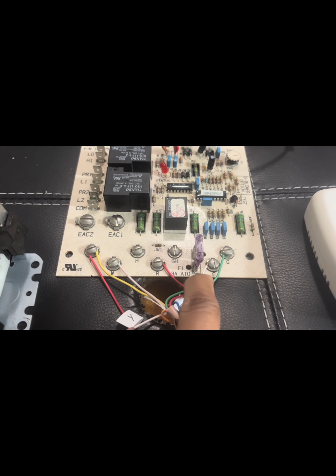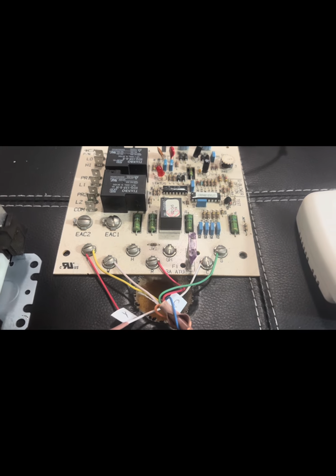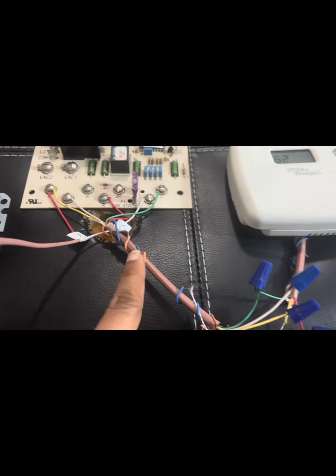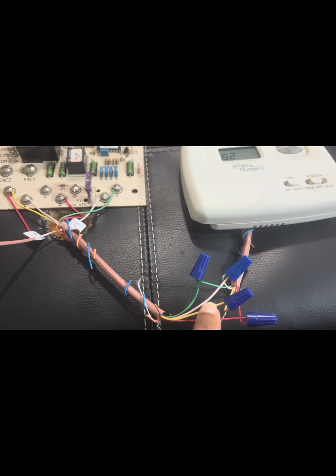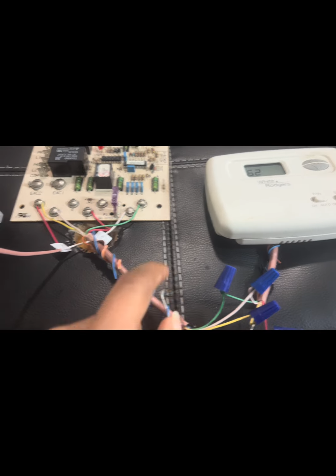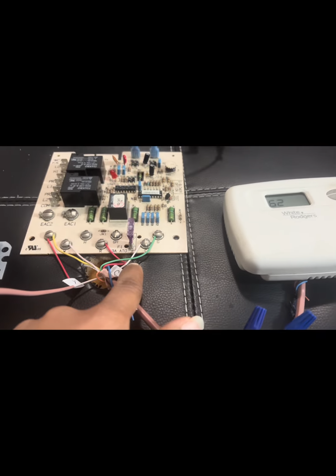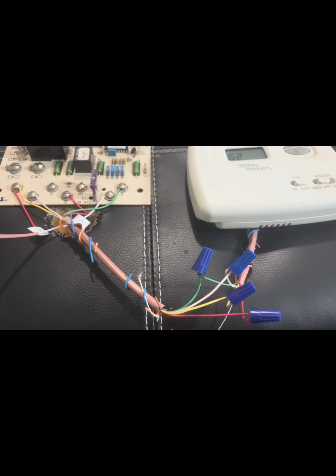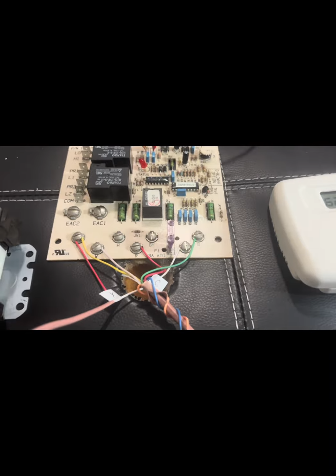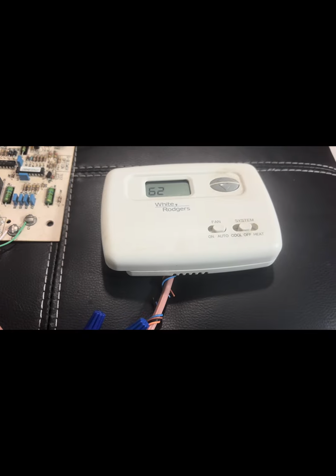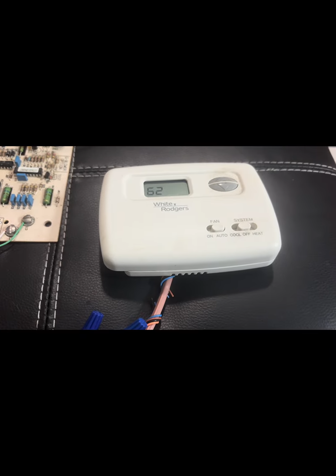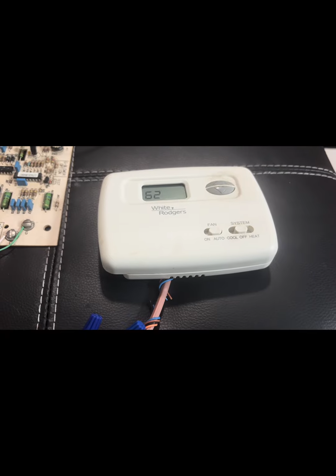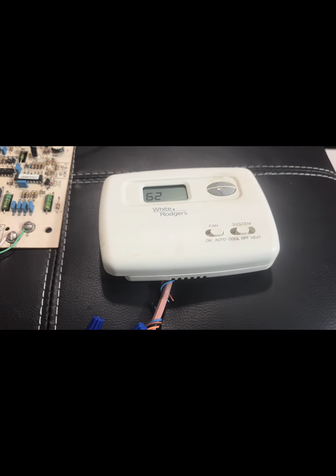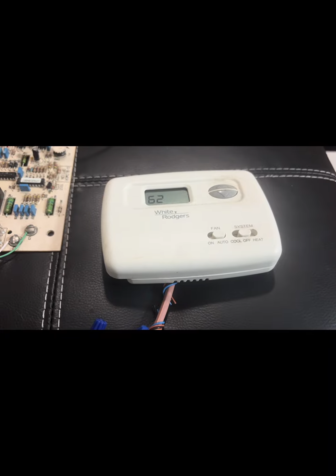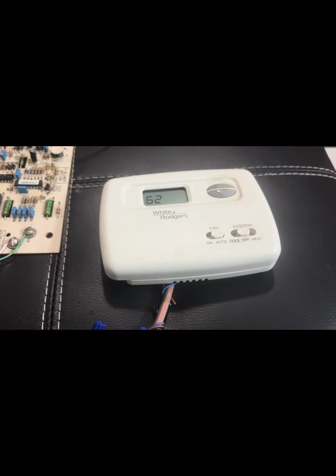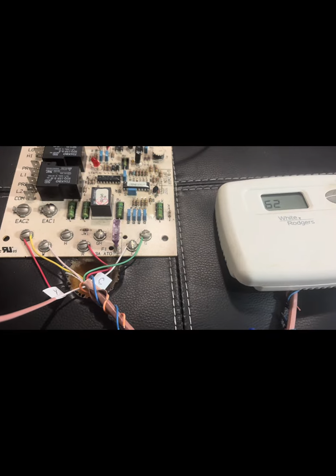Then you connect the matching wires to your thermostat. So we have that going back to your thermostat. And if we had a common one for this thermostat, we will also do the same thing. But this one doesn't have the C terminal. This way, when the thermostat sends R to Y, power flows, the furnace relays that Y signal to the outdoor unit, and the C wire completes that 24 volt circuit. The condenser contactor energizes, the compressor plus fan starts to run.